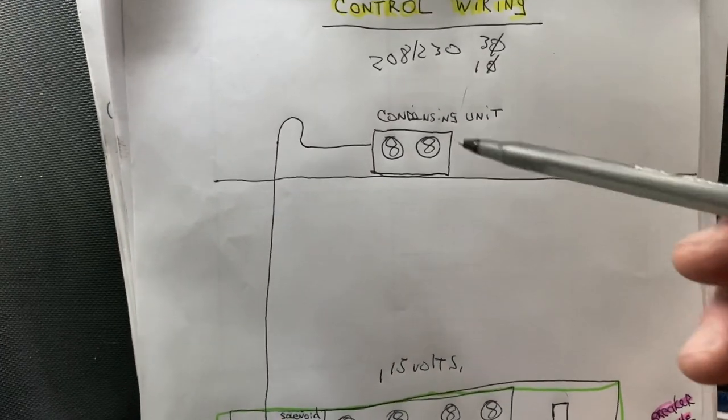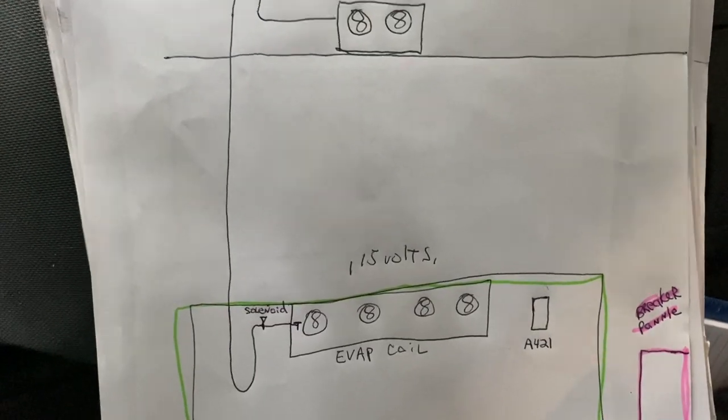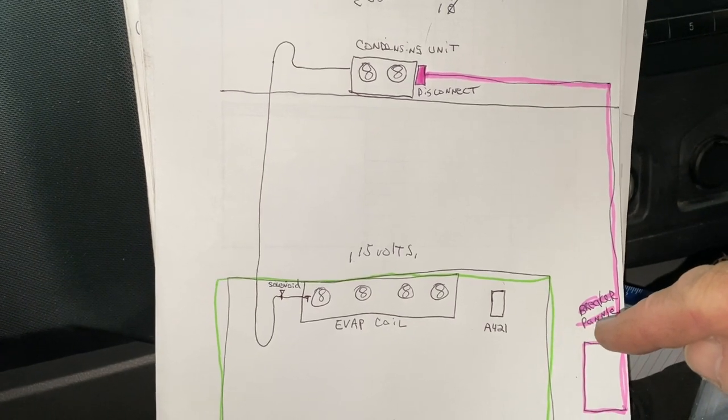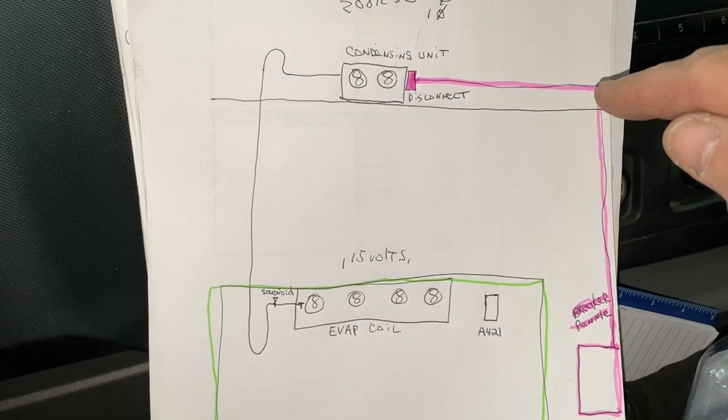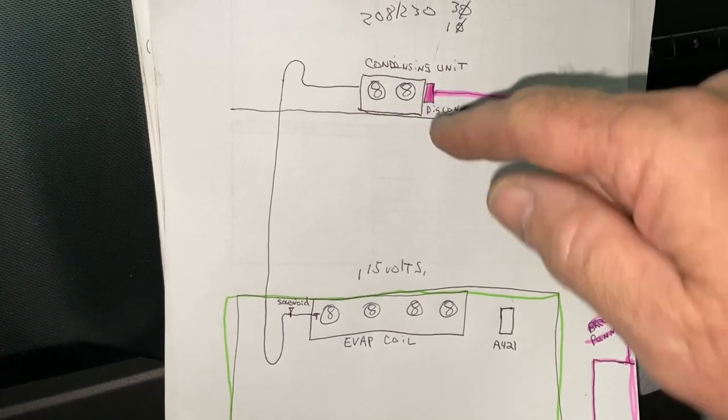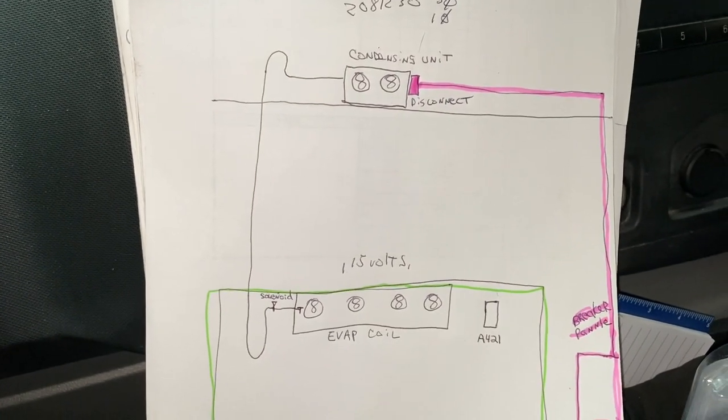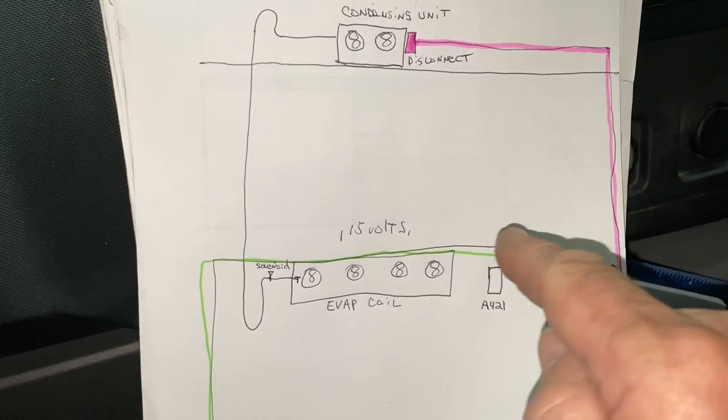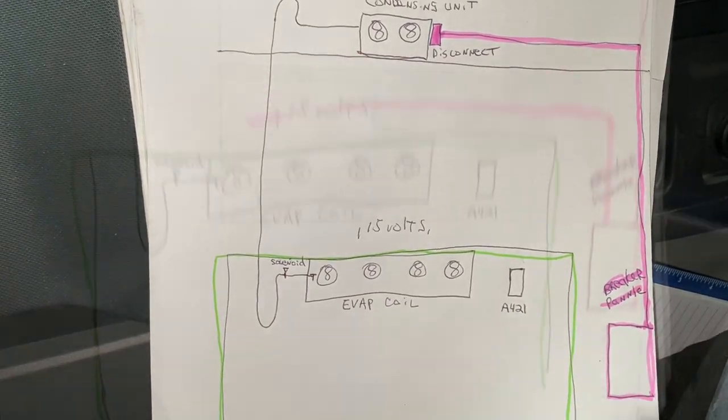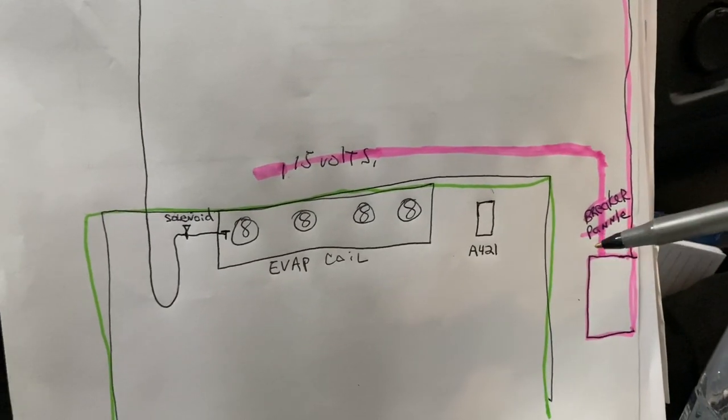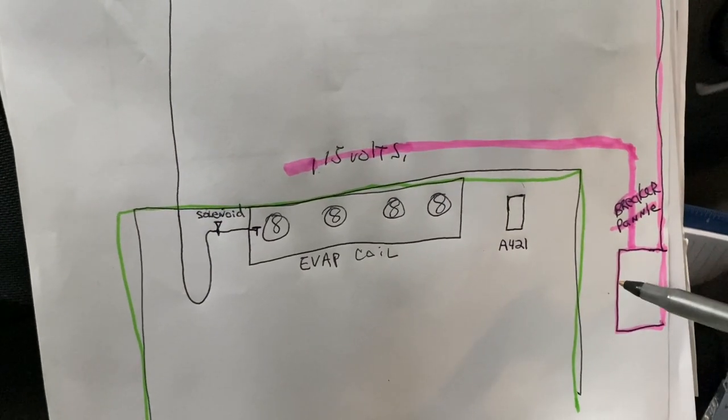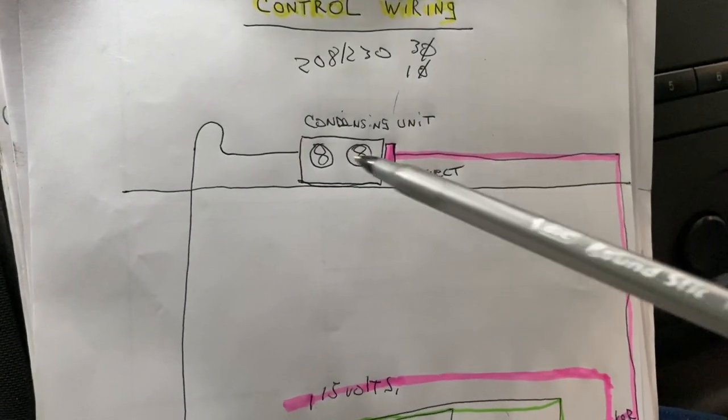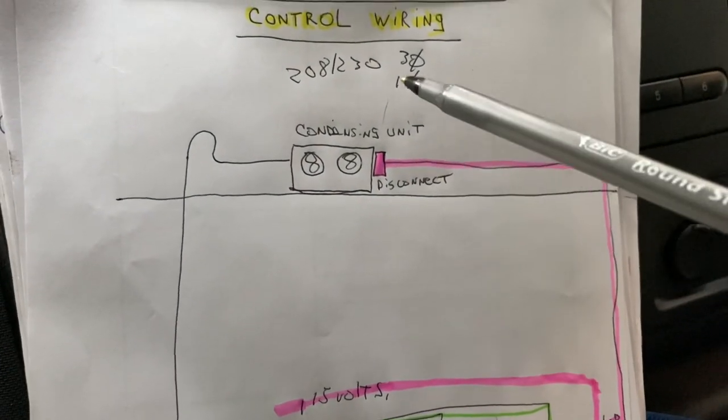That's going to be a separate circuit on the roof for your condensing unit. From your breaker panel in a conduit up to the roof to your disconnect. Separate circuit. Now we're going to have a 115 volt circuit that comes over here to our evaporator coil. This will usually be a single pole breaker. This will be a three pole breaker if it's three phase for the roof unit, or a two pole breaker if it's single phase.